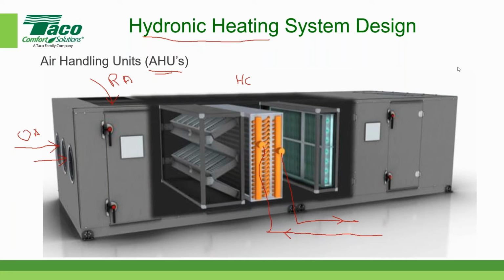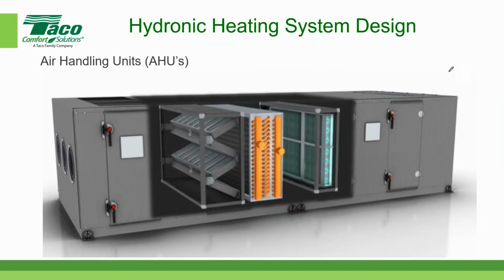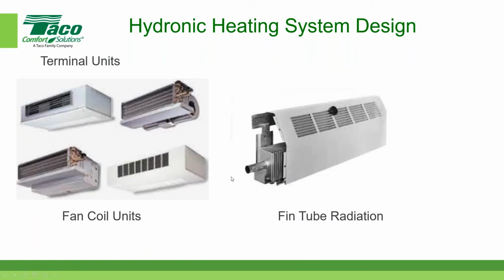Okay, and then we start getting into the details a little bit more on the terminal components that you find. So one category is called fan coils. They come in a variety of shapes and sizes, and typically they have a finned tube coil, which you can see here, and they typically have a fan, which is where the name fan coil comes from. And again, you have these piping connections. Here are a couple of piping connections. There's one there and there's one there. And so the hot fluid would flow into the coil through the piping connections.